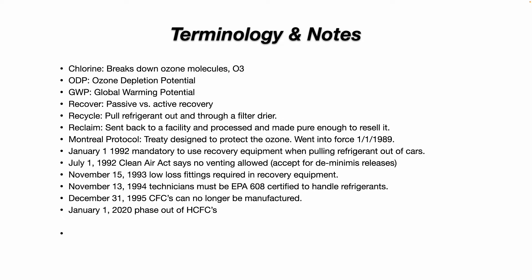Reclaiming refrigerant means you pull it out of a piece of equipment and send it back to a factory or facility authorized to process, clean, and make it pure enough to sell to virgin refrigerant standards. The Montreal Protocol was a treaty designed to protect the ozone layer. It went into force January 1, 1989.